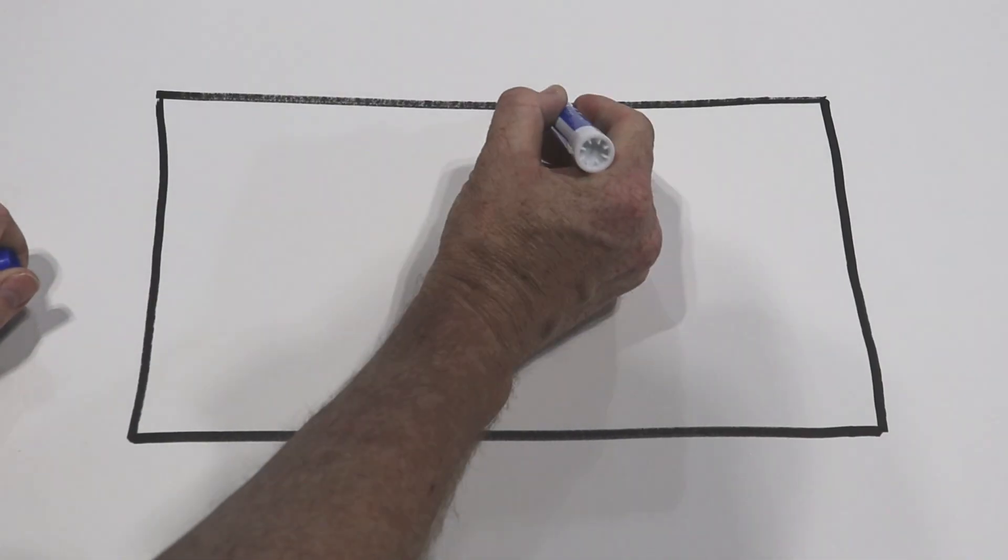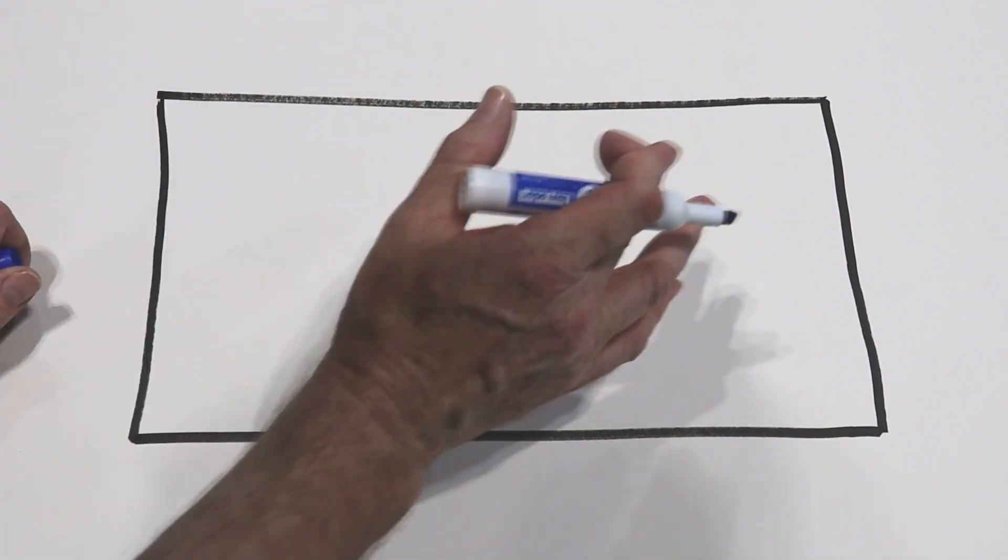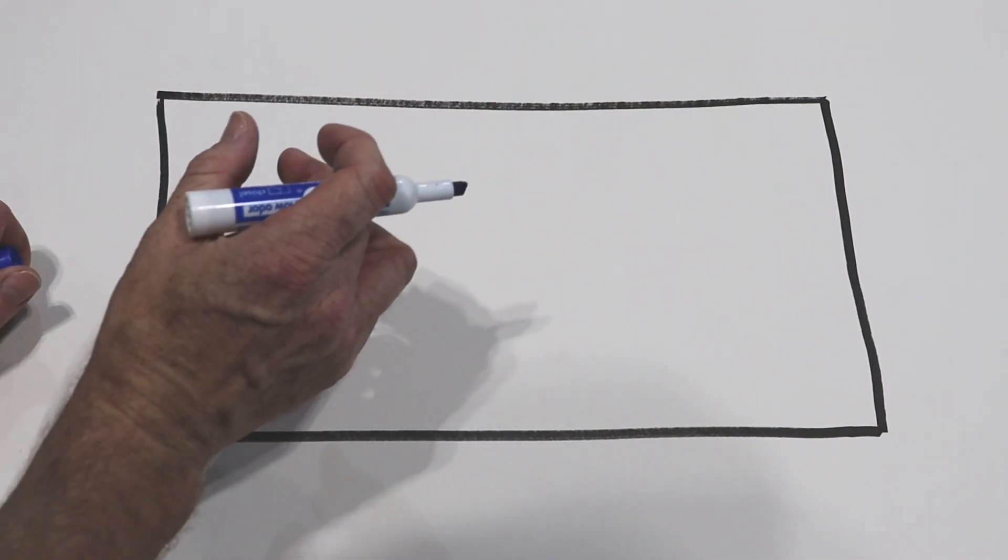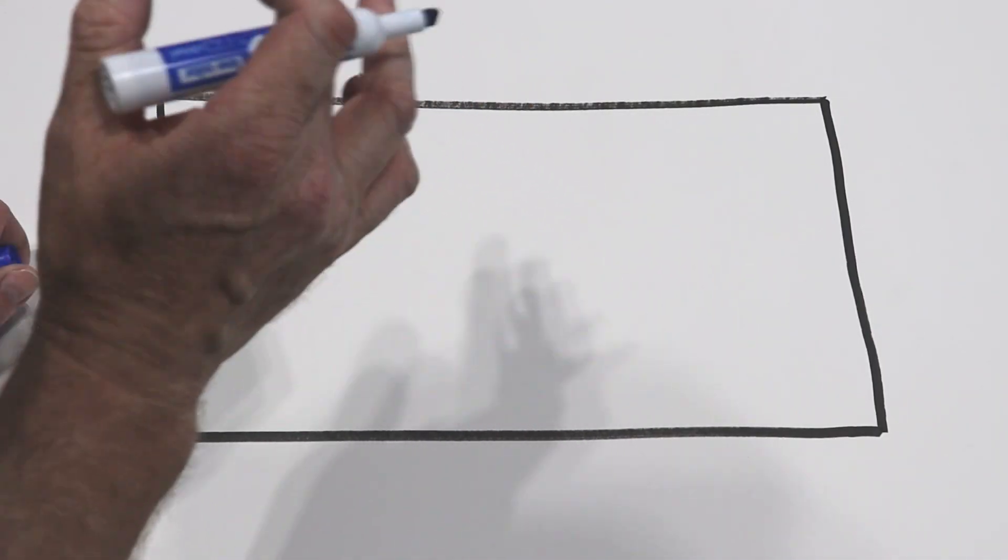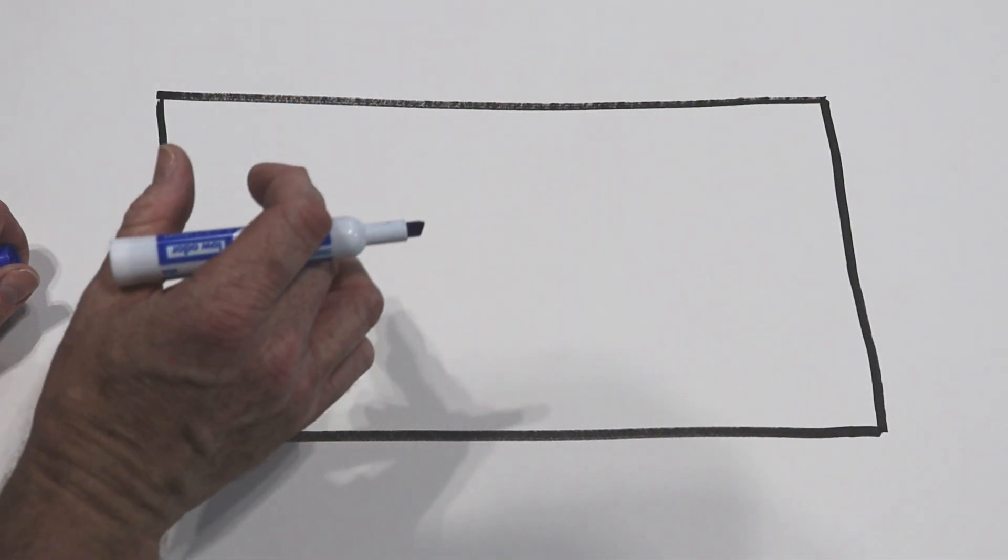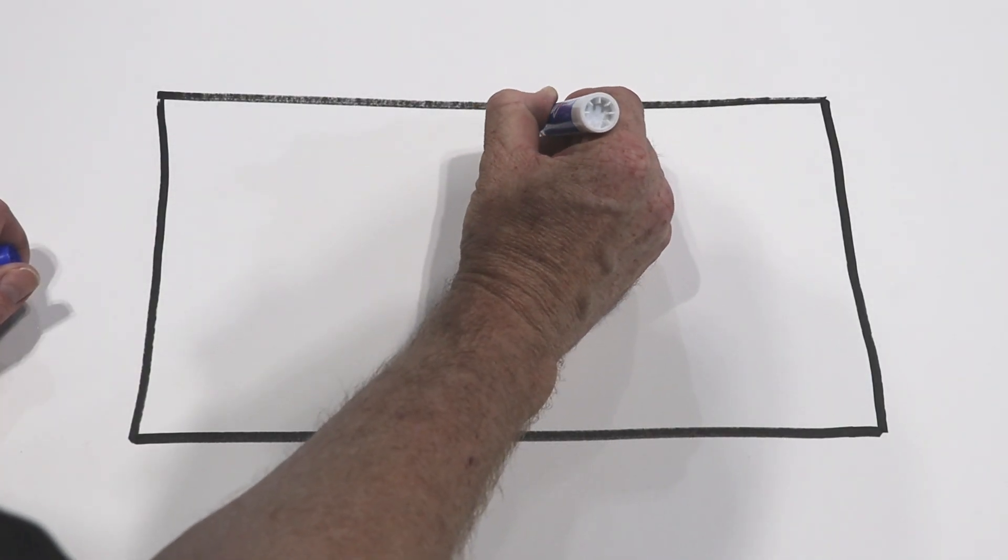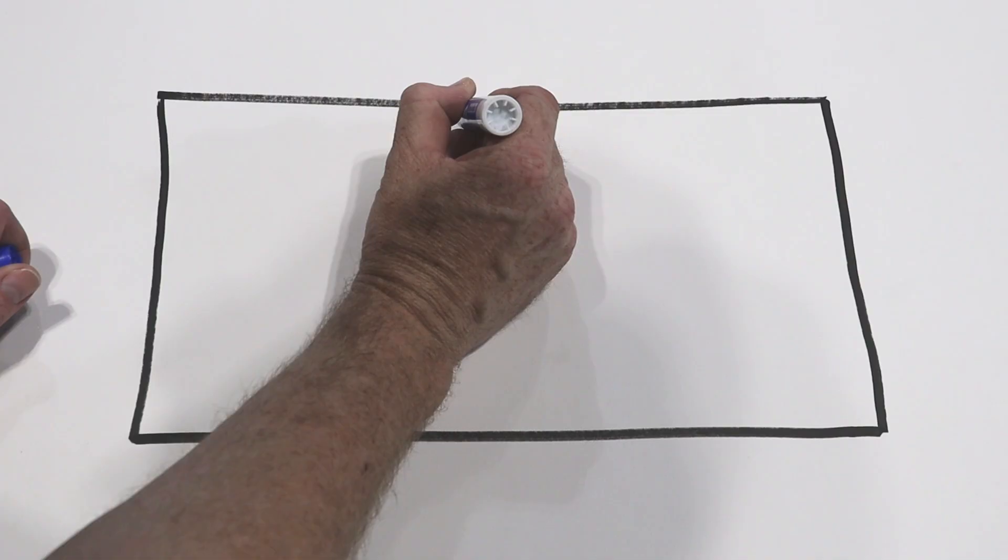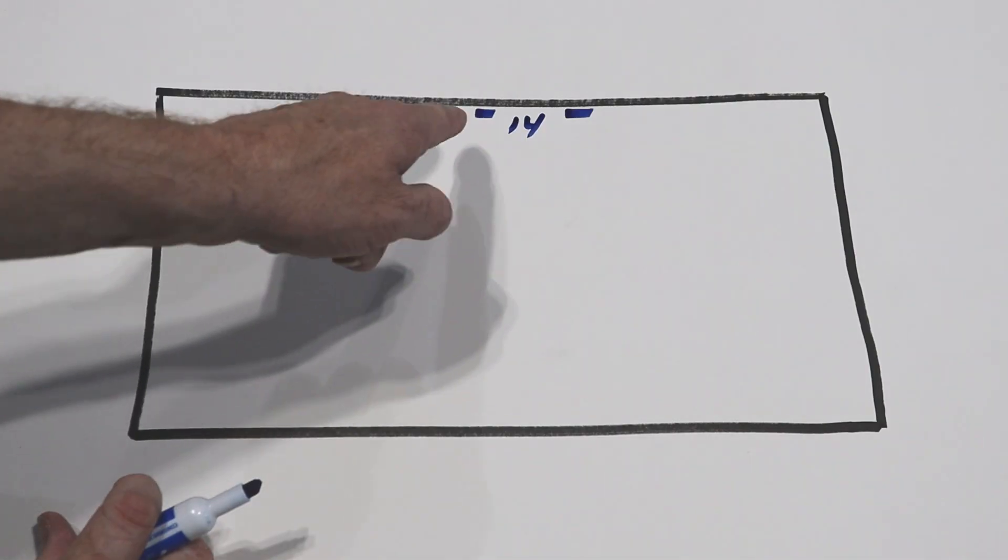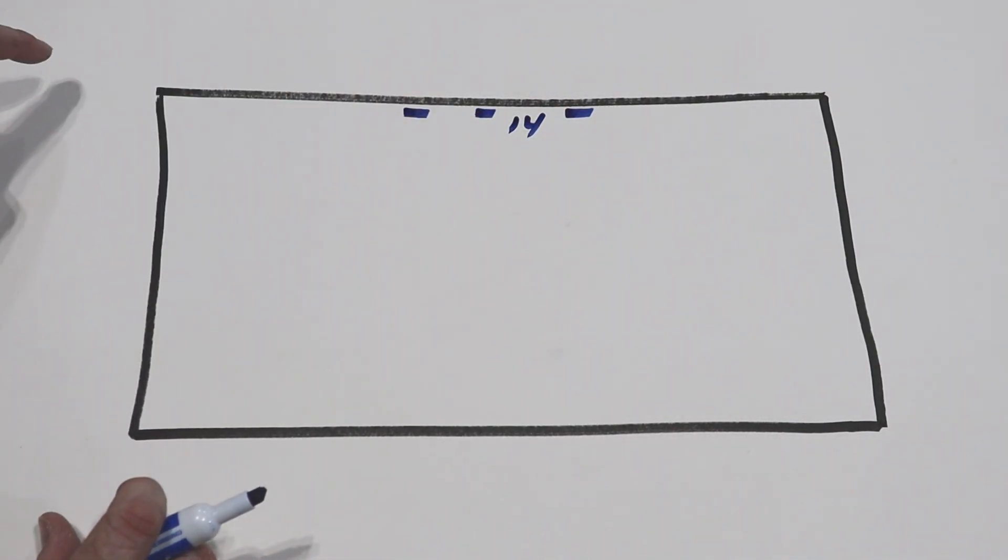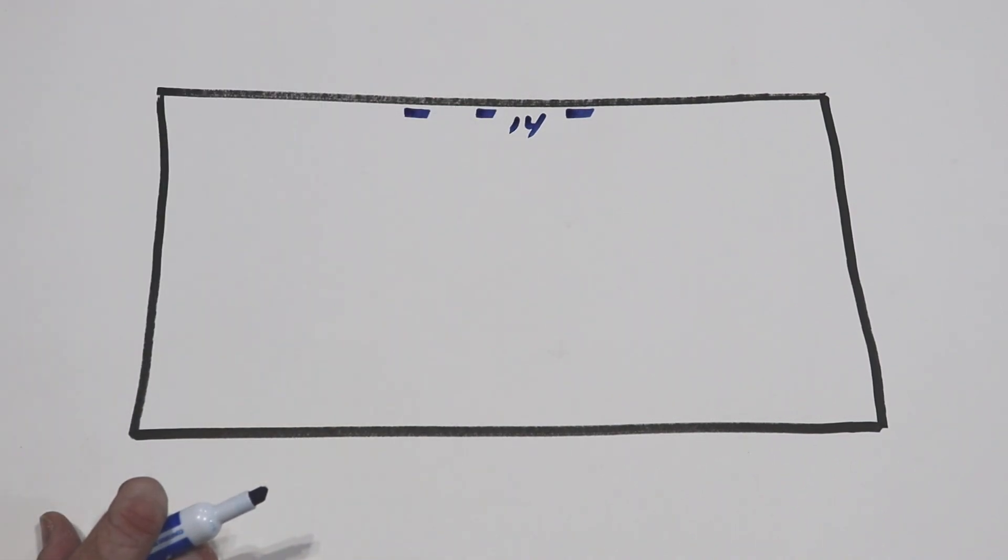Let's say right over here, this is where I'm going to have my stereo system and Xbox, PlayStation, big screen TV, the whole thing. So I've figured out, either using the name plates or going online and figuring out how much amperage each device draws. Let's say it draws 14 amps when everything's said and done. So I might only put in say like three outlets right here where I can plug a bunch of stuff in. I know that if I put in a 20 amp breaker, the max I'm going to draw is about 14 amps, so I should be safe. I shouldn't trip anything here.